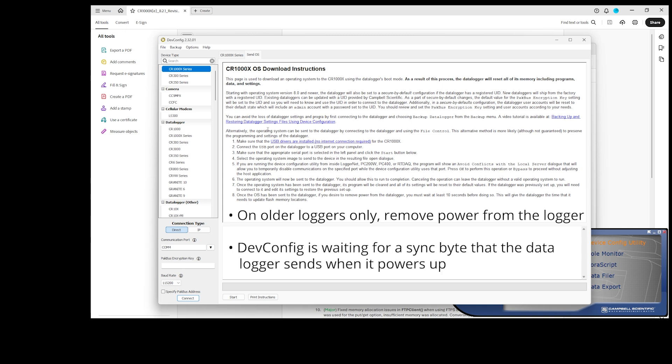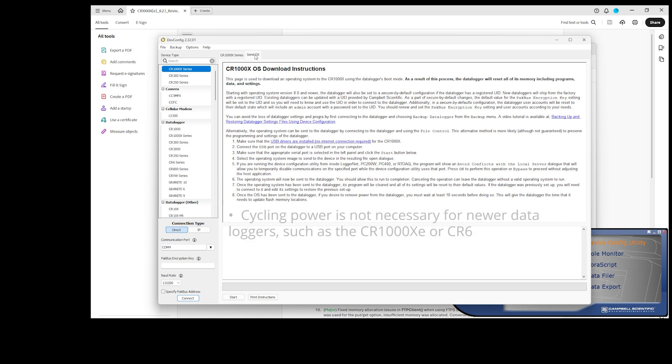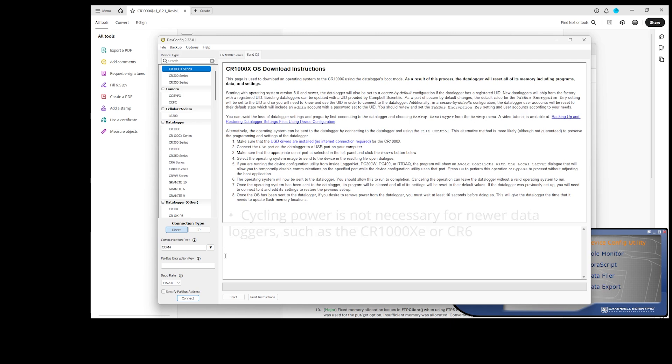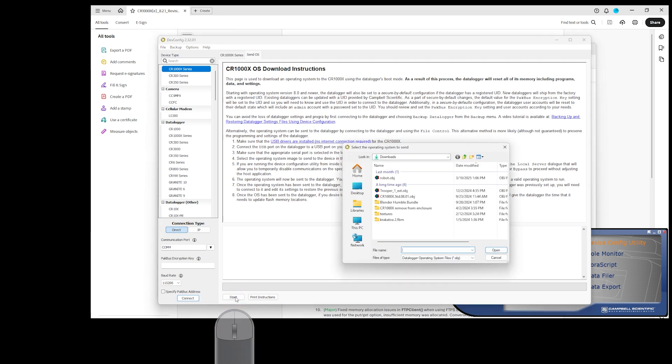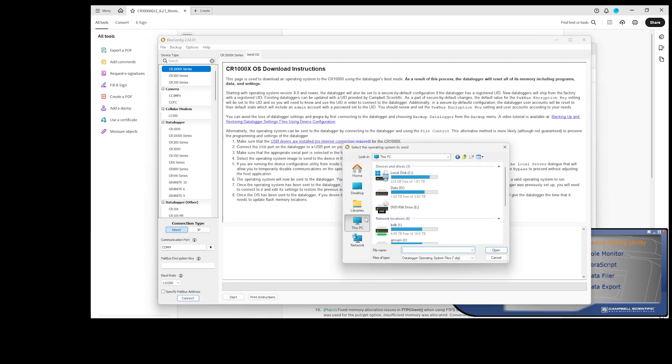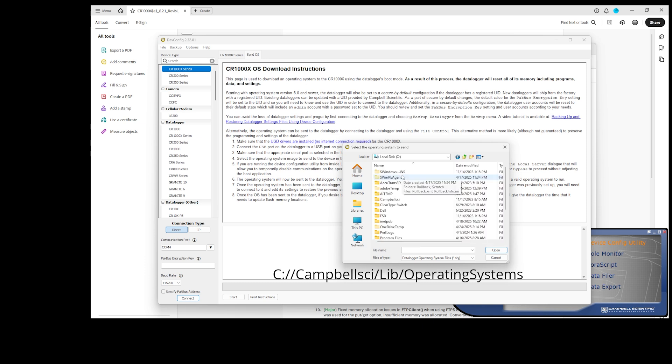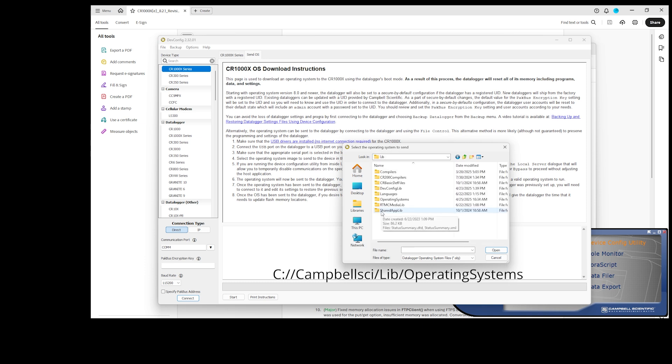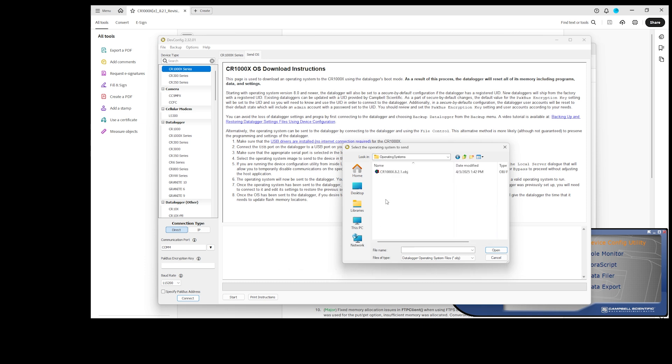The OS update will not begin until Device Configuration Utility receives a sync byte that the data logger sends when it powers up. Cycling power is not necessary for newer data loggers, such as the CR1000XE or CR6. Start. Navigate to the new OS. It will be in the C-Campbell-Sci-Lib-Operating-Systems folder. Select the OS file and click Open.